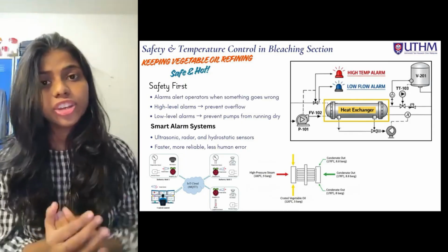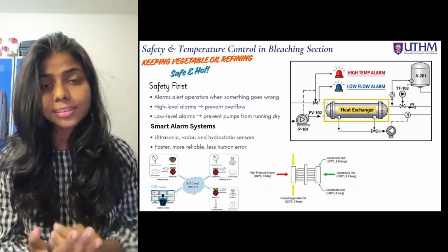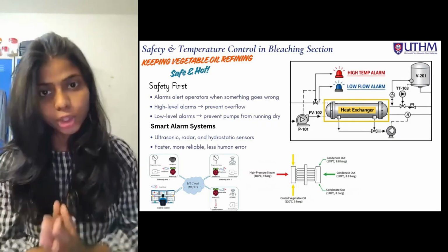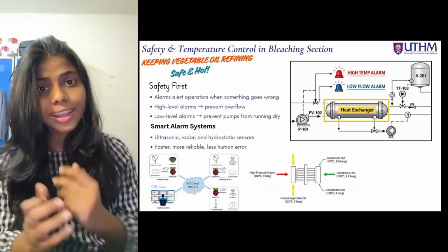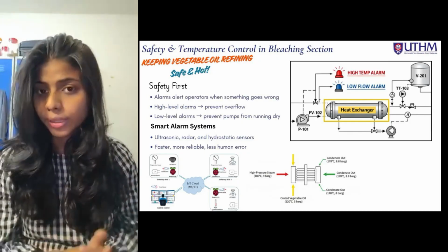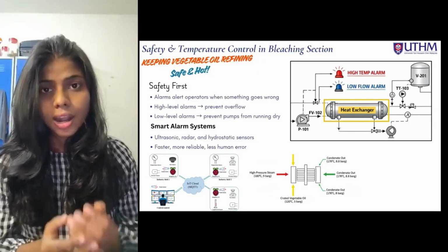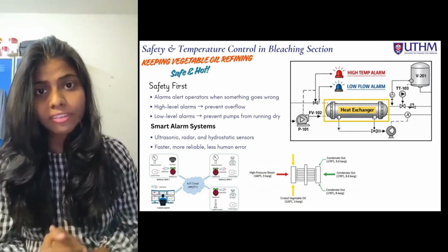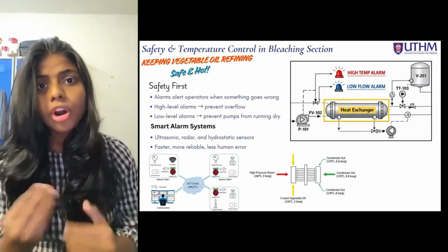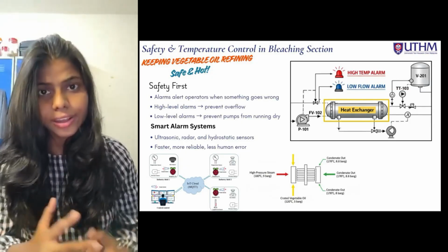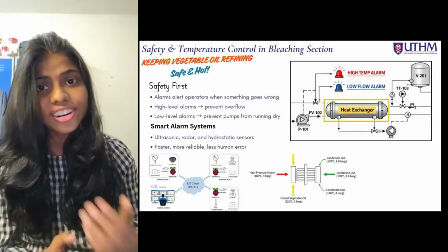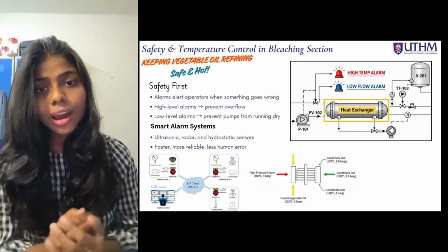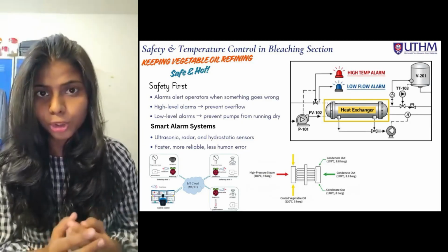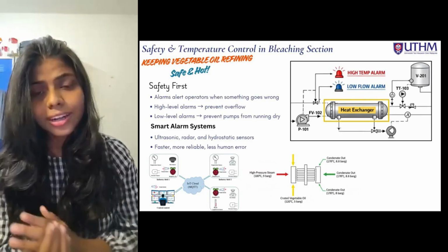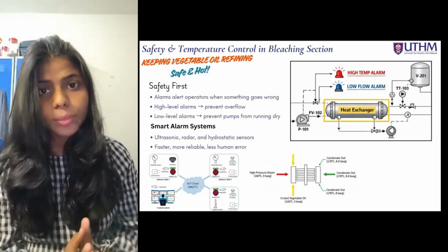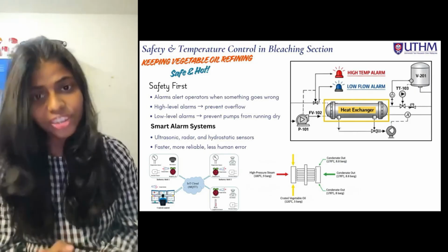Safety is very important in vegetable oil processing. The interlock and alarm system acts as an early warning system to protect the workers and equipment. Alarms alert operators when the condition like level, temperature and pressure exceed the safe limits. For example, a high level alarm prevents the tank from the overflow, while the low level alarm protects the pump from running dry. Modern refinery use advanced sensors such as ultrasonic, radar and pressure transmitters, which are more accurate and reliable than traditional float alarms. To prevent alarm flooding, standards like ISA 18.2 are followed, so only critical alarms are displayed. Smart alarm system can also trigger automatic shutdowns, improving plant safety and efficiency.